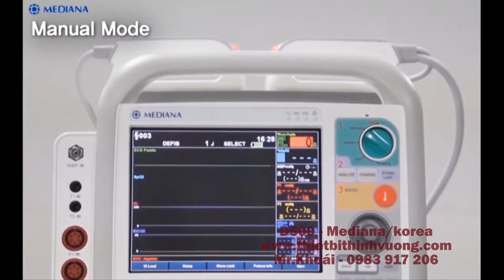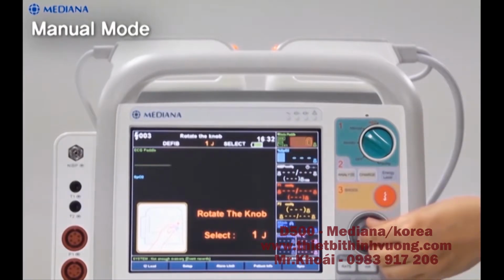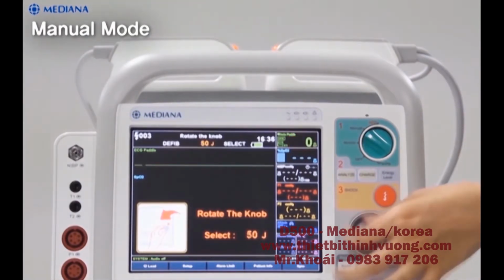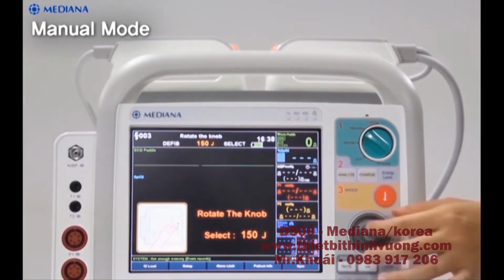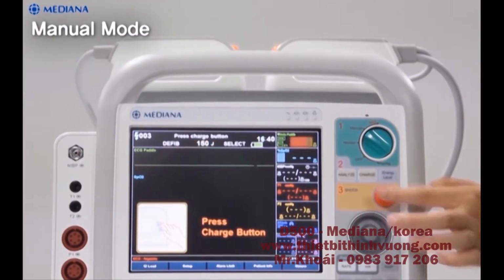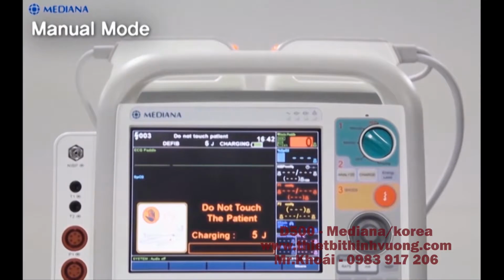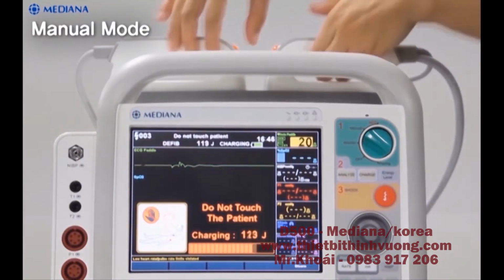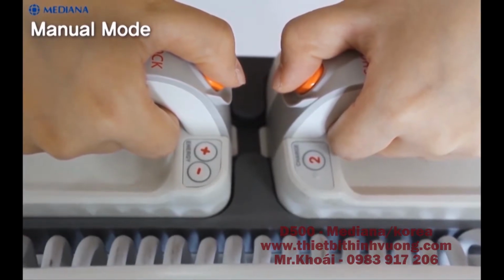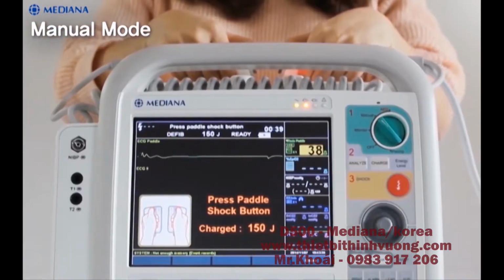To select the energy setting, press the Select Energy Level button and rotate the multifunction knob to the desired energy level. Energy choices range from 1 to 200 joules. To choose a higher value than 200 joules, enter the service menu. And if you want to charge the energy, press the Charge button. There are 2 charge buttons, on the paddle and the front panel.